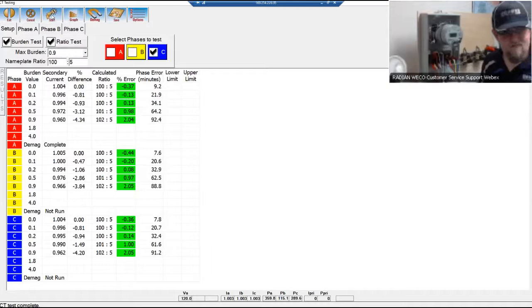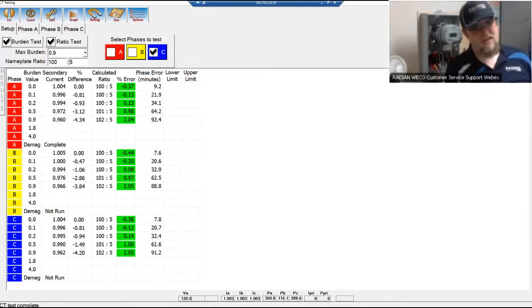You can see A phase, you can see the burden values that it was tested at. Then right over that, the secondary current that was read during that burden test step. The percent difference between no burden added as well as adding in burden. So you can see the percent difference between no burden and that burden step. The calculated ratio of that CT during that burden step. The percent error between primary and secondary. And then the phase error between the current phase angle being read by the secondary, the current phase angle being read by the probe and the primary in minutes. And then repeat for A, B, and C.